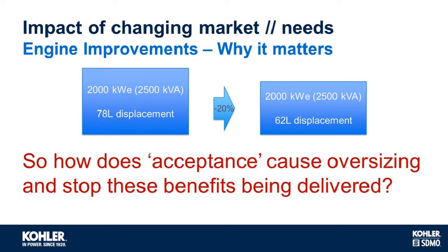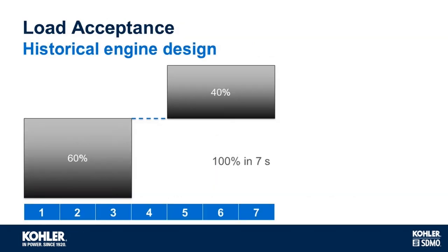So how does this acceptance of old norms cause oversizing and stop these benefits from being delivered? Historically, specifiers used an initial load step of 60% as a benchmark to align to the market expectations. So let's look at this example. The engine is started, then a 60% load is applied. The generator recovers within 3 seconds, the G3 standard. And then a further 40% is applied and it recovers again. So now it's fully loaded, 100%, and back to steady state voltage and frequency within 7 seconds.